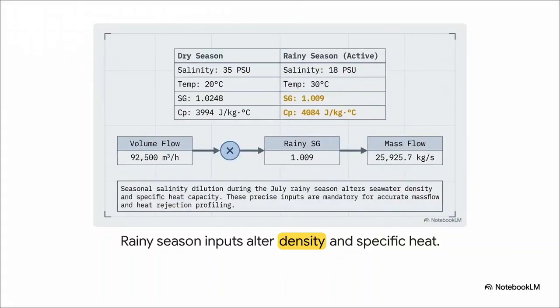And of course, we can't just ignore Mother Nature. During this specific assessment, the July rainy season was diluting the seawater. That dropped the salinity from 35 PSU all the way down to 18 PSU. And it raised the temperature. This directly alters the seawater's density and its specific heat capacity. Notice how the specific gravity drops to 1.009? We actually have to multiply our volume flow by this specific rainy season gravity to get our true mass flow of just under 26,000 kilograms per second. These exact inputs are mandatory. If we just lazily use dry season numbers right now, our entire heat rejection profile will be completely wrong.